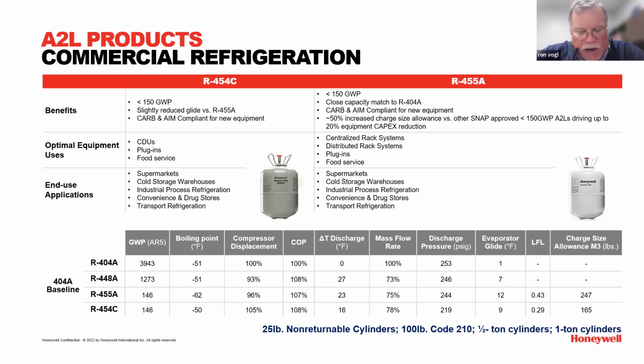Yeah, that's great, and here's a question that came up. I was doing a seminar last week, and a lot of the leak detection equipment is really good these days, even wall mounted stuff. But with an A2L, you have to do something at 25% of the LFL. So pretty low, right? Then the issue is, how specific can it be? Right now, you buy a general detector, we use them in the lab, and pretty much any HFC or HFO it'll pick up.